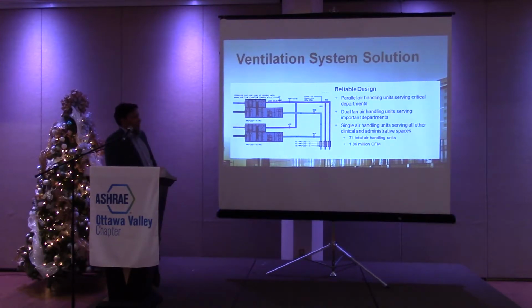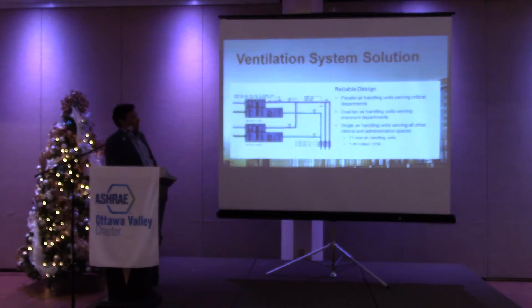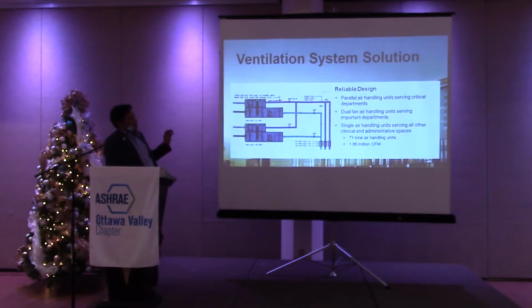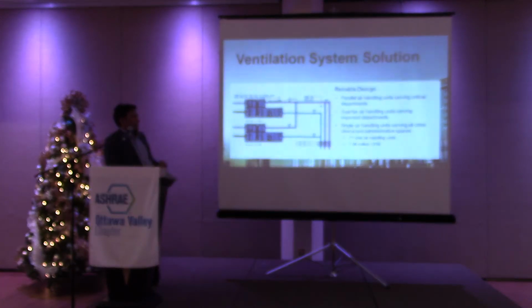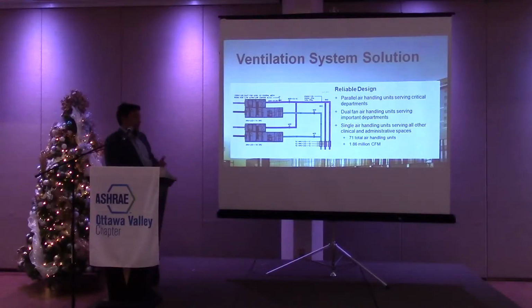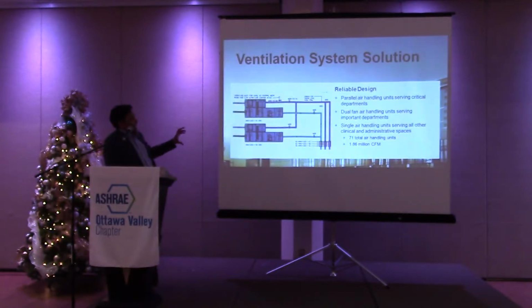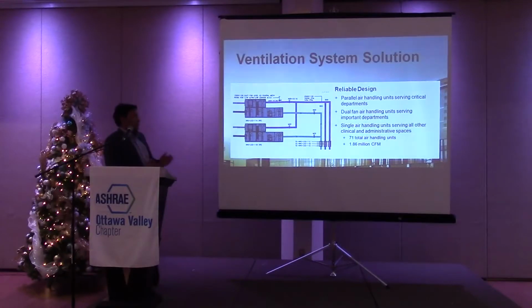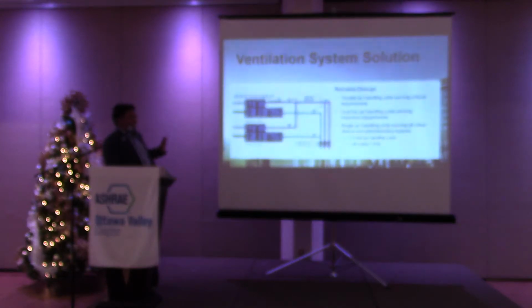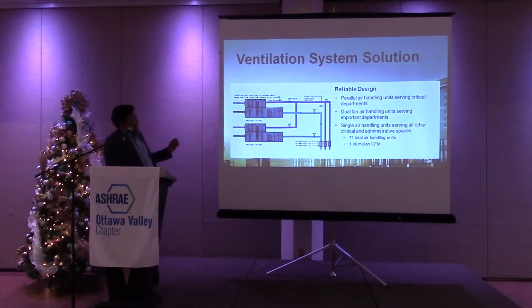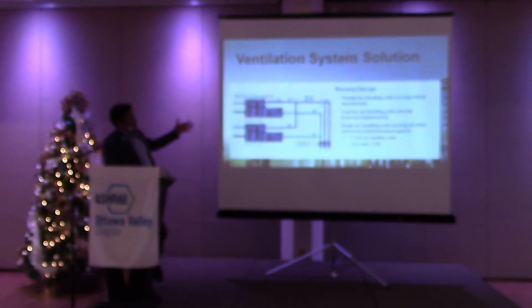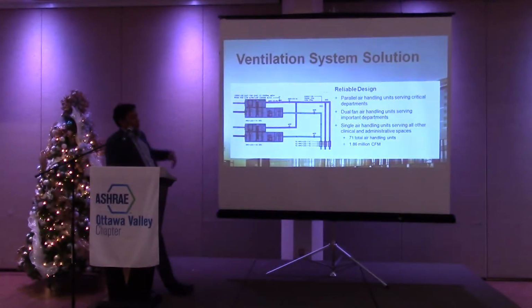So for the ventilation system, fan energy was a huge part of trying to improve energy efficiency. In our case, for all the critical areas of the hospital, places like critical care, ORs, the birthing units, operative delivery, we had parallel air handling units serving those spaces. Each air handling unit was sized for 100% of the load, but we operate them at 50% of the load, and I'll get into that further. So this allowed for those 24/7 spaces filter changes and maintenance of the entire air handler to be done.